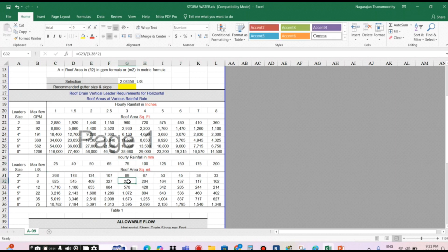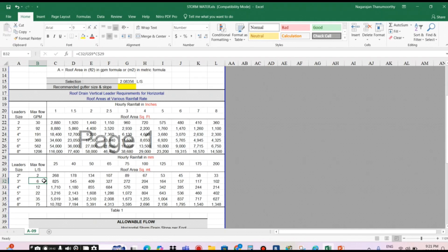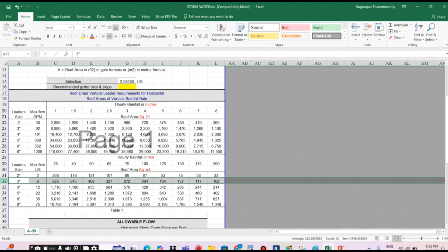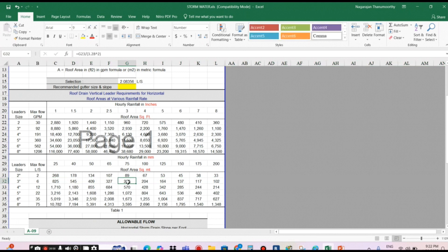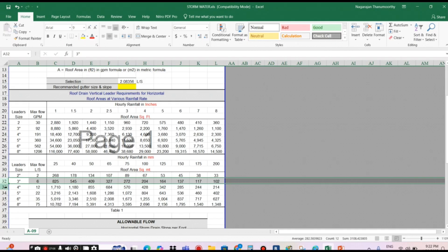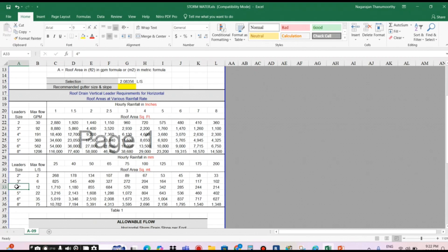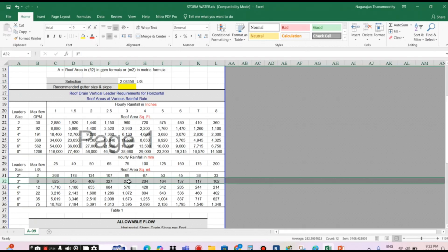The table shows that up to 272 square meters is acceptable at this pipe size. In our case it is 100 square meters, so we are within the limit. However, if the area were 300 square meters with a flow of 5.2 liters per second, you would first select 3-inch for the vertical pipe based on flow, but since 300 square meters exceeds the 272 square meter limit, you cannot use 3 inch and must go to 4 inch. In our actual case of 100 square meters, the vertical pipe is 3 inch.